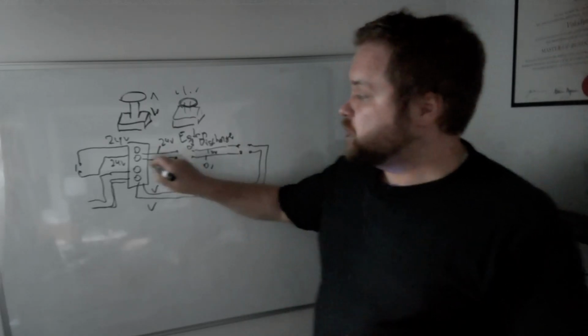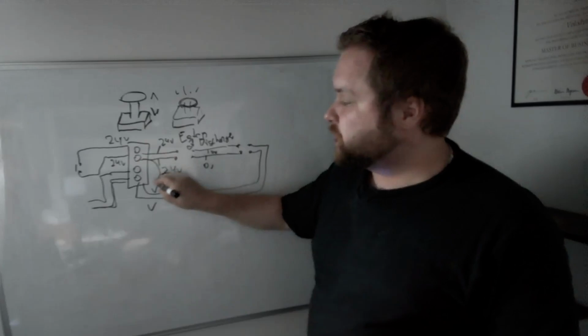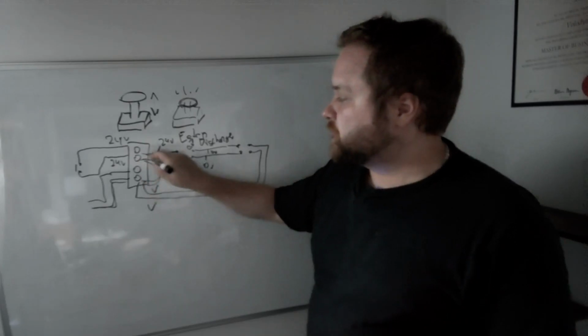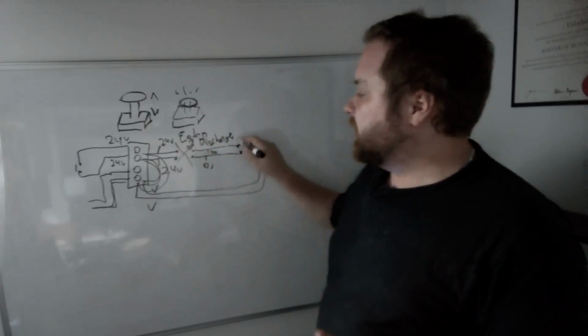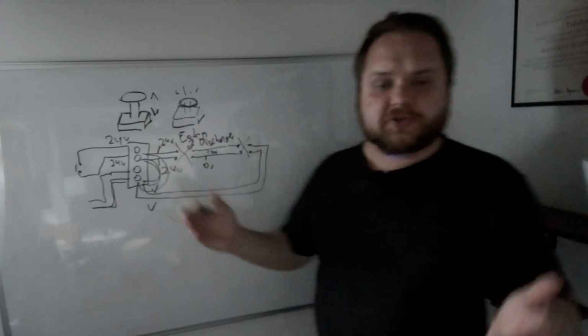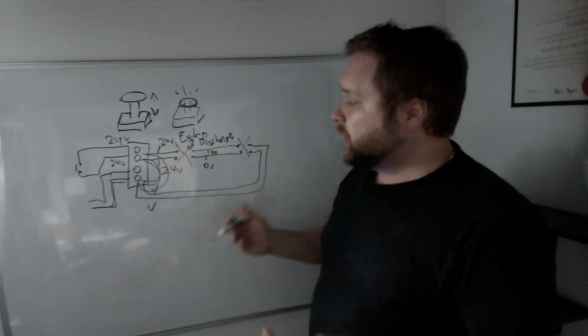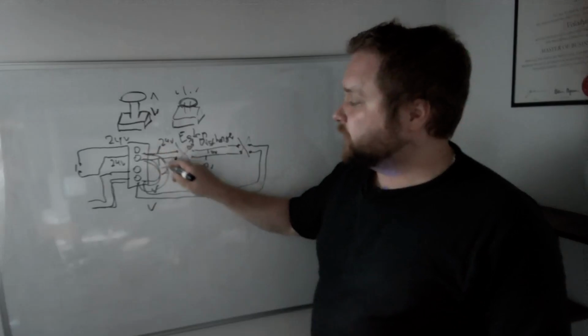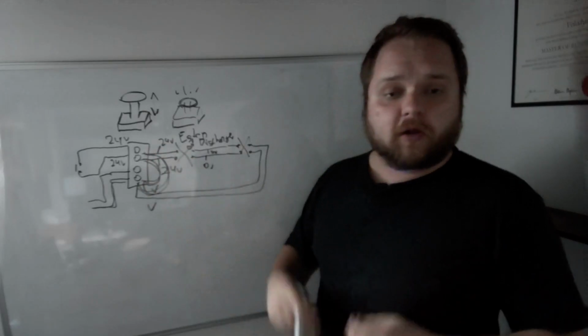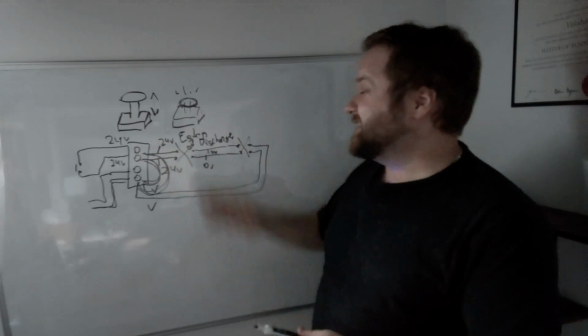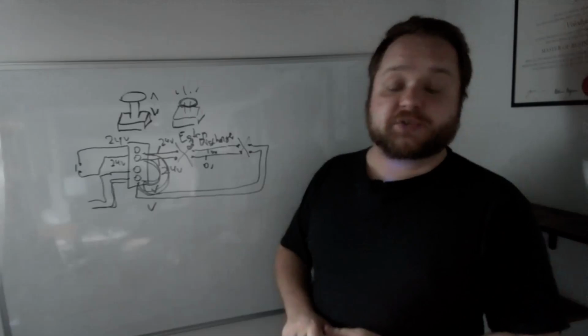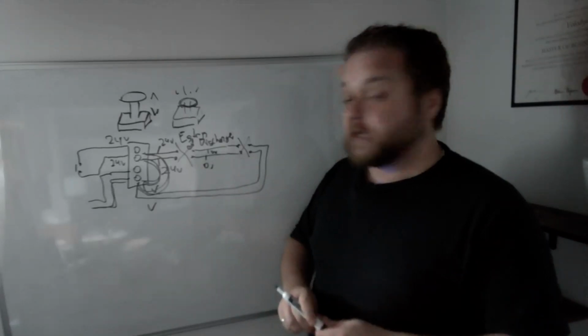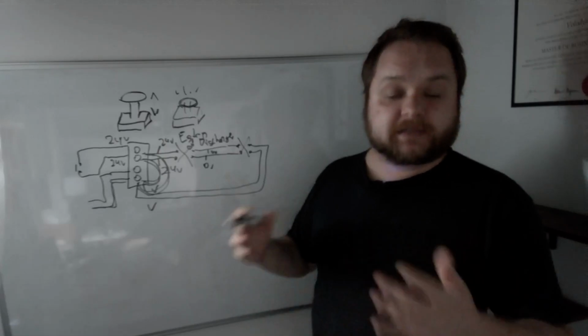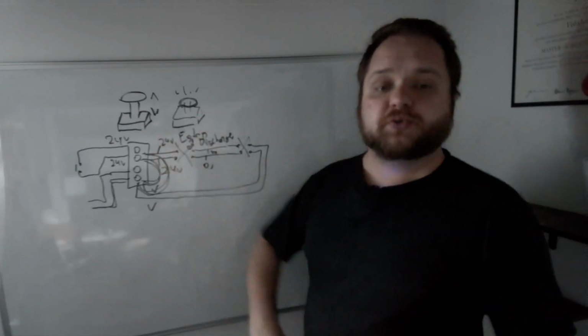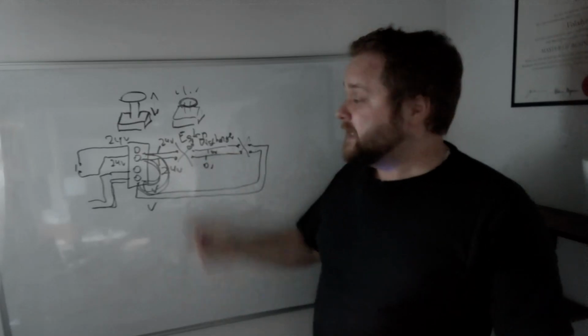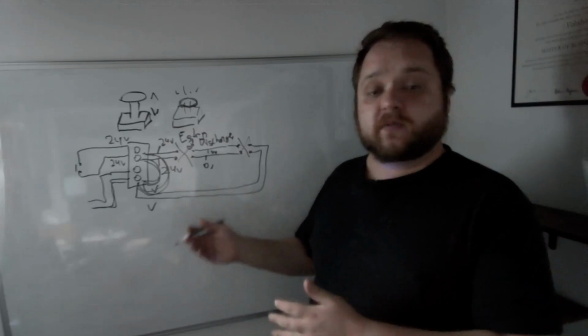But in this scenario, you have two channels of 24 volts. And so you can shortcut basically on the same inputs, you can shortcut the 24 volt signal bypassing whatever is here. And so as an electronics tech or engineer or even director level, you should understand that all it's really doing in this case is looking to make sure that you have 2 points of contact going through the circuit. And so really all you've done by placing these jumpers in place, you have disabled the entire chain of safety that enables that specific relay. And like I keep mentioning, this is not something I would recommend doing, but I do see instances where this is basically required in order to troubleshoot some other issues or maybe to allow a specific part of the process to run as we understand what is going on with specific precautions in place.